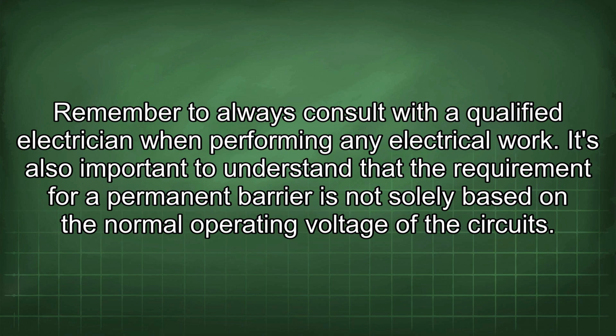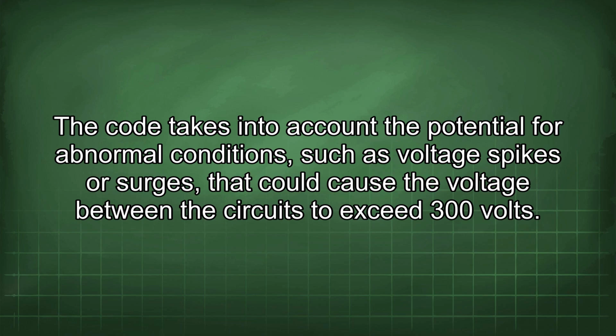It's also important to understand that the requirement for a permanent barrier is not solely based on the normal operating voltage of the circuits. The code takes into account the potential for abnormal conditions, such as voltage spikes or surges, that could cause the voltage between the circuits to exceed 300 volts.